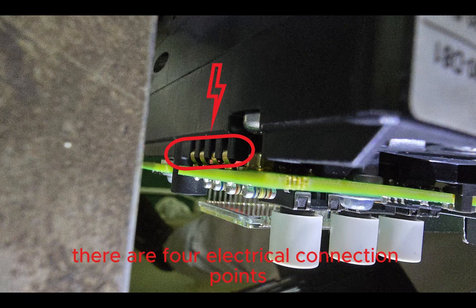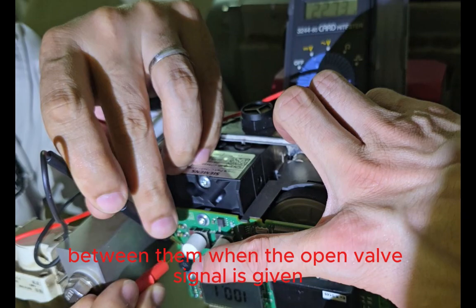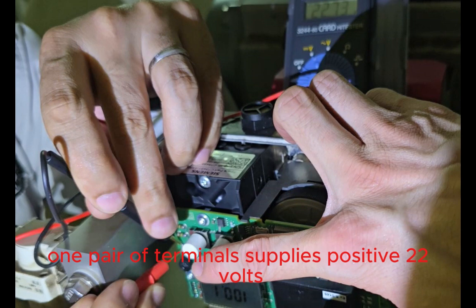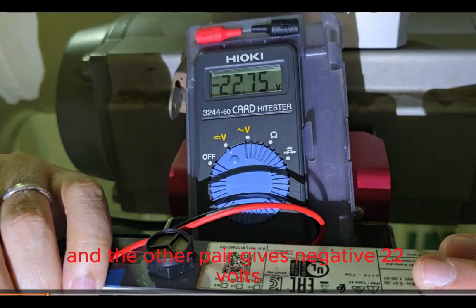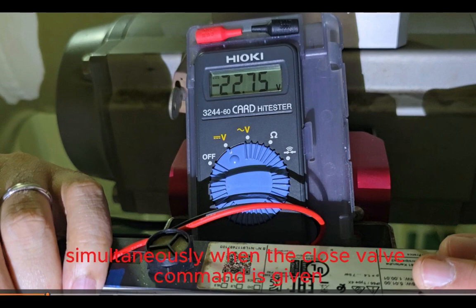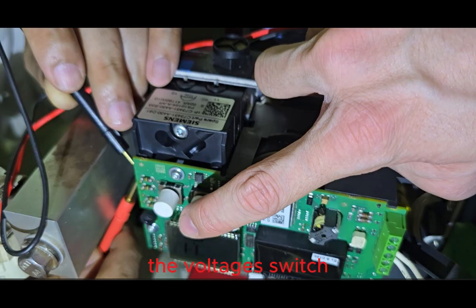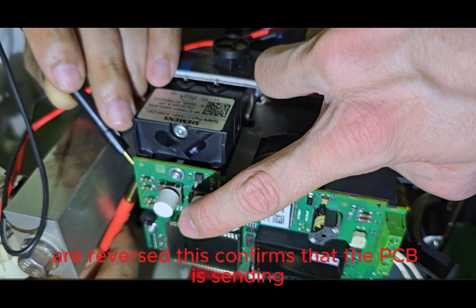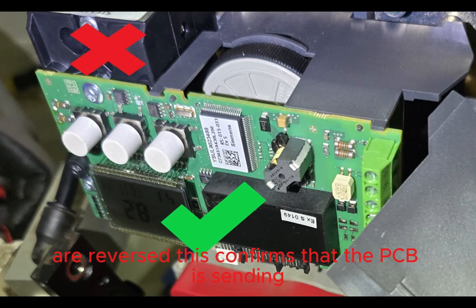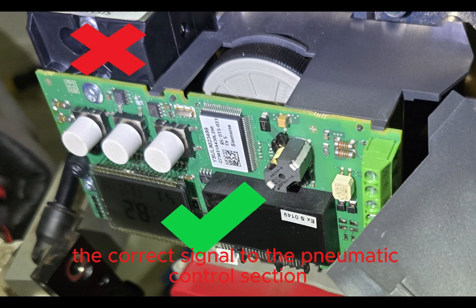Then I checked the voltage supply from the PCB to the pneumatic block. There are 4 electrical connection points between them. When the open valve signal is given, one pair of terminals supplies positive 22 volts, and the other pair gives negative 22 volts simultaneously. When the close valve command is given, the voltages are reversed. This confirms that the PCB is sending the correct signal to the pneumatic control section.